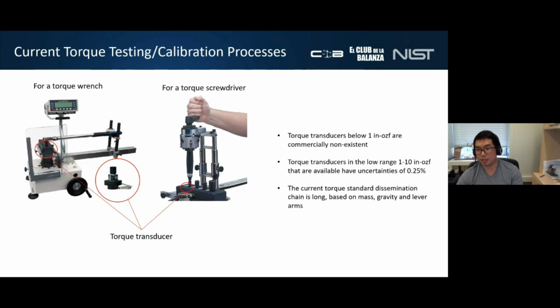If the torque value measured by the system is within tolerance, the tool passes verification and everyone's happy. If not, and this is kind of wasteful, they typically just chuck or discard the tool, though sometimes they'll adjust it back to be within tolerance.